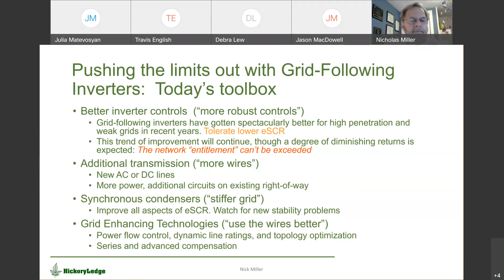You can fix the issues by adding more transmission. You can stiffen the system with synchronous condensers. That last case was mitigated by turning a couple of old, possibly-to-be-retired coal plants in the Western interconnection into synchronous condensers, similar to the experience Julia showed of adding condensers. There are other things we can do to stiffen the grid up.